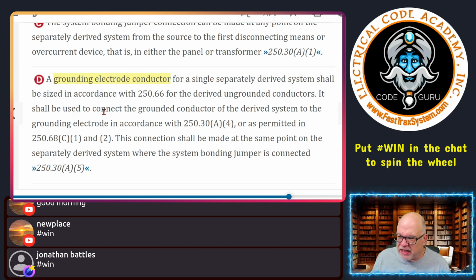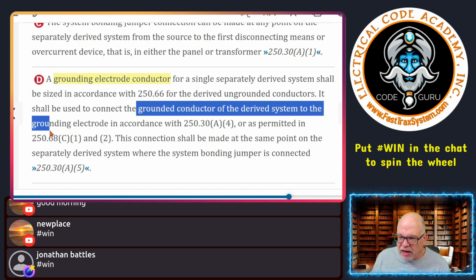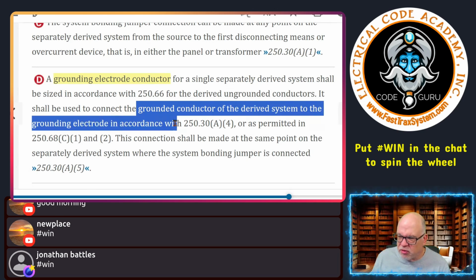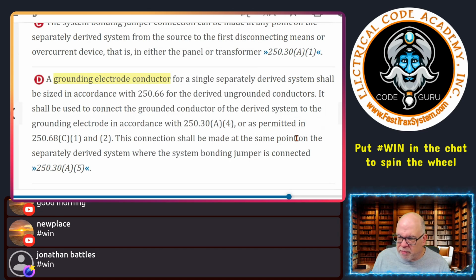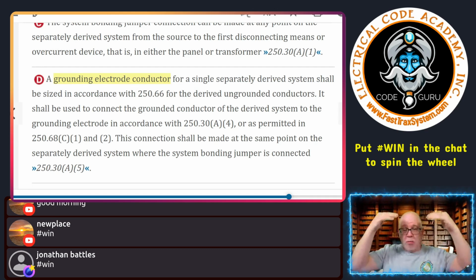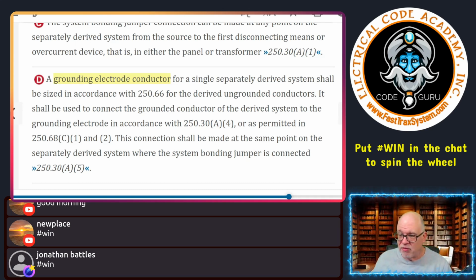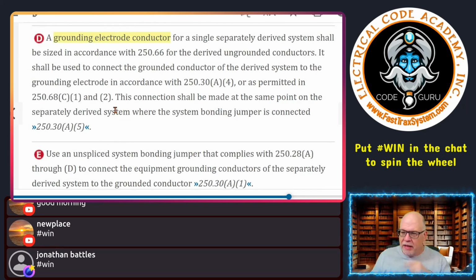It shall be used to connect the grounded conductor of a derived system to the grounding electrode in accordance with 250.30A4 or as permitted in 250.68 C1 and C2. So that is some allowances for connecting to a water line under specific conditions or to building steel that will extend that connection to the electrode. That's important because you could have transformers on multiple floors. So that does give you some allowances there. Now, this connection shall be made at the same point on the separately derived system where that system bonding jumper is installed. So let me show you what it's talking about.